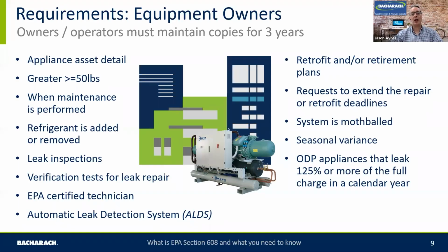With that asset, if you're going to do any retrofit or retirement, and by retirement I mean removing it out of service, you need to capture that information. And that could be a plan, a detail. Again, records need to be held and available to the EPA. Other types of processes and reports that need to be held: extensions to any repair deadlines, you need to have those available. Systems that are mothballed, so that could be a chiller that you don't use all the time, then you remove that refrigerant from the system whilst it's not in use. That needs to be captured and available.